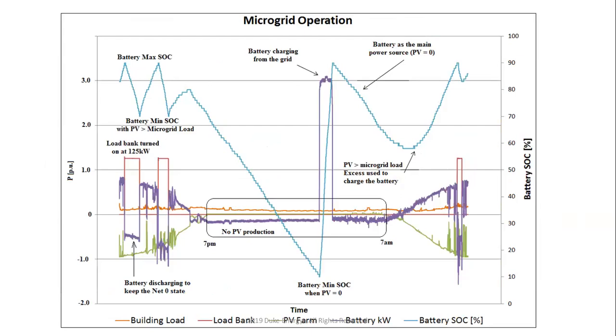And orange is a load within the building. Red is the load that we can actually control ourselves, right? So essentially, as long as the green stuff, as long as the PV is greater than our load, we charge the battery. Once the battery reaches 90%, which is right there in the middle, on the left side on the top where it says battery max SOC, we turn on the load bank. We can actually curtail the PV, but in this case we don't do it because we have enough load that we can turn on, right? So we turn on the load bank at 125 kW.